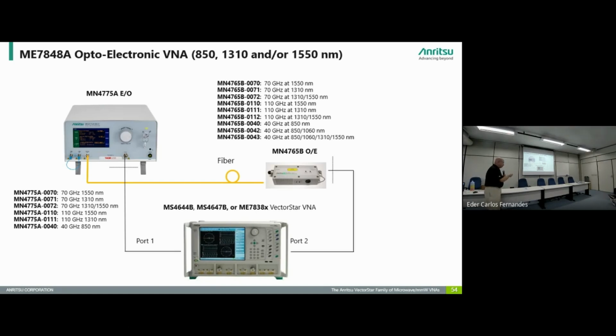It doesn't make you very confident about the measurements you're making. So again, the OE is critical because that's what sets the derivation from national standards. That's what sets the accuracy and uncertainty of the measurement. And then the EO is nice to have because it's very stable and can be characterized based on the OE. So the two do go together. But if all you ever test is modulators, then of course you don't need the EO, because your device will always be here. But if you're doing photoreceivers or photodiodes, you're going to need a stable optical transmitter that you can characterize based on that OE module. So that's how it works.